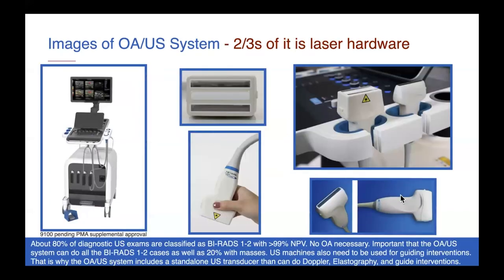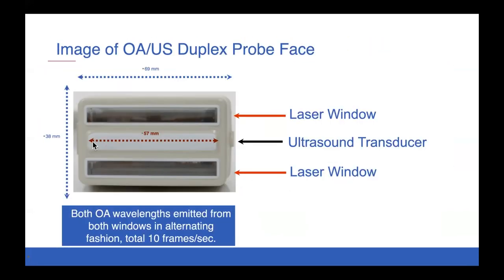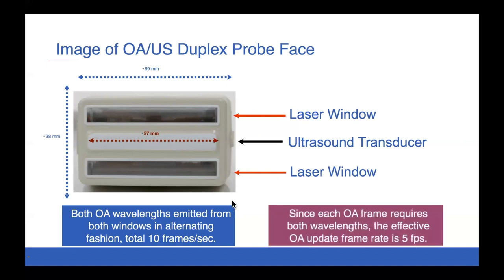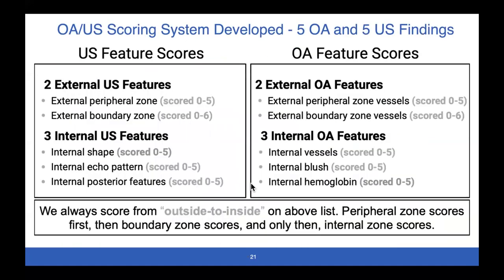The standalone ultrasound probe is 5 megahertz to 18 megahertz, and it's 50 millimeters wide. We can fire anywhere from 35 to 55 frames per second on ultrasound, but we can only fire 10 signals per second of OA, and it takes both a long and a short wave to create a frame, so the color frames are updated at 5 frames per second. There's a difference in frame rate between OA and ultrasound, which requires slow, steady movement during video sweeps, because if you move too fast you can create spatial and temporal misregistration.